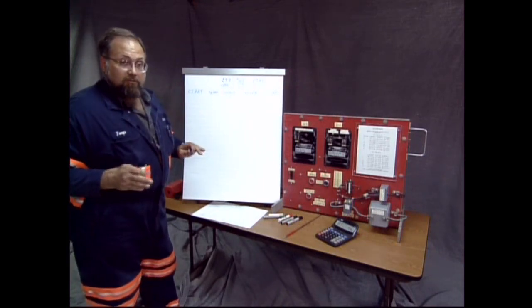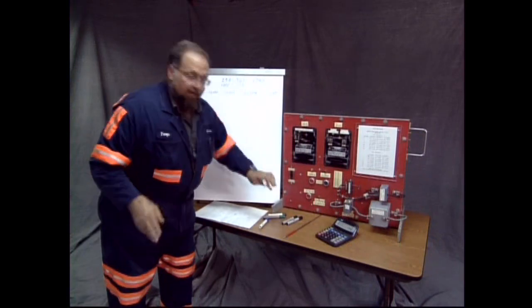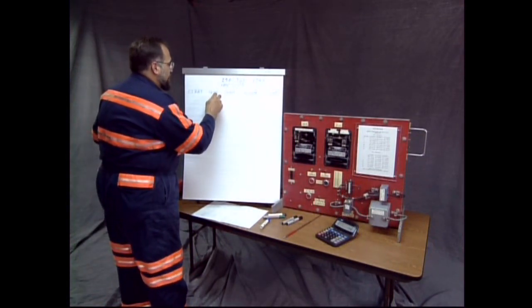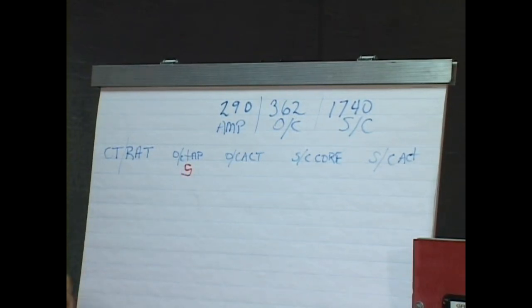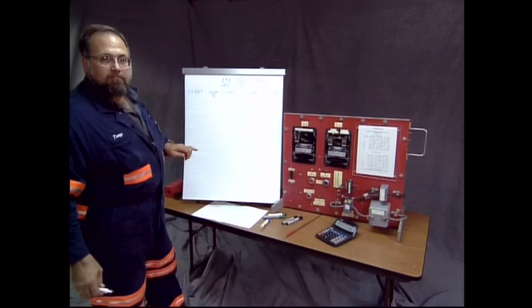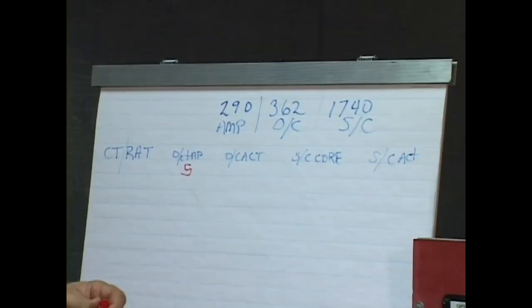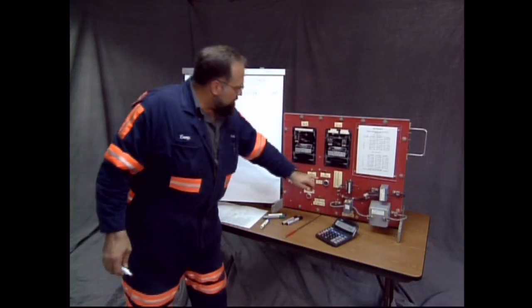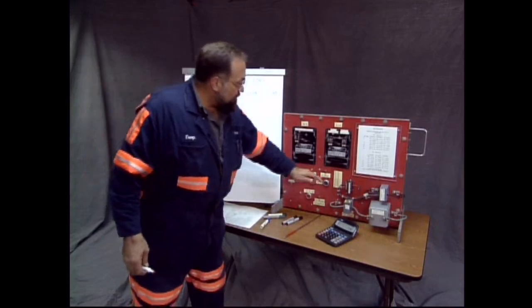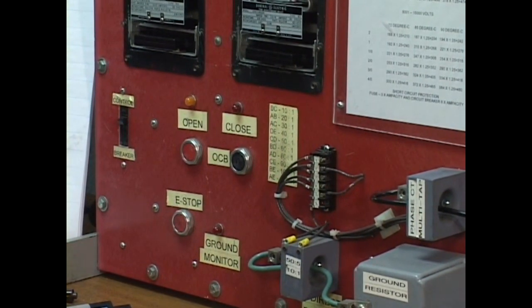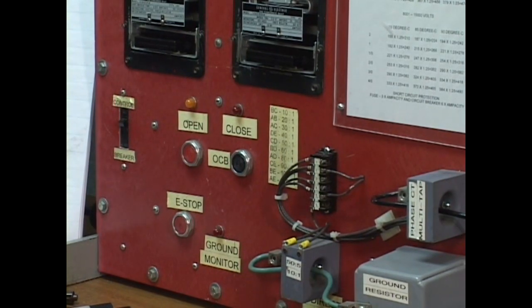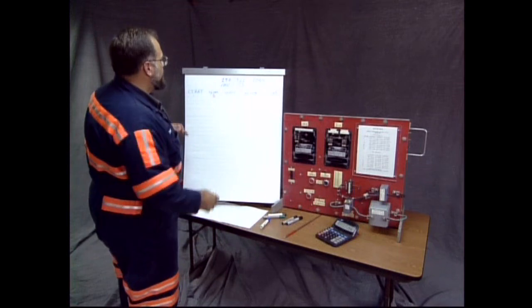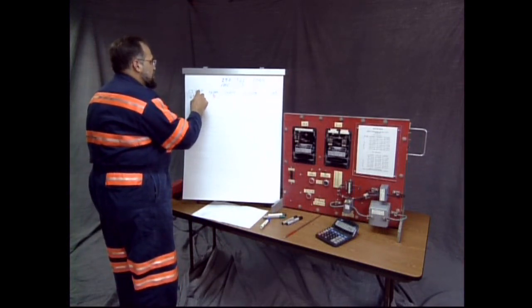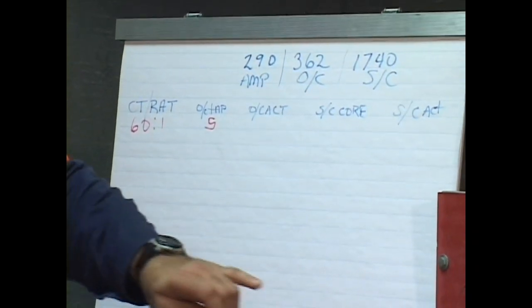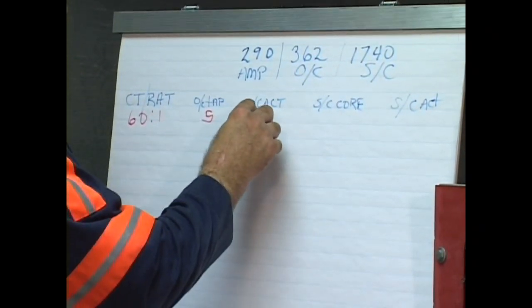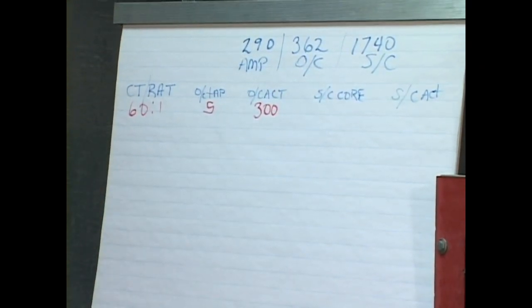The first one that you would figure, you're going to automatically choose the magic number 5. That's the ampacity of your CT secondary, magic number 5 for a tap. Now you divide your 362 by 5. What would that give you? A 70. 70 would be 350. That's as close as you can get. But we don't have a 70. All these ratios available, there are two that are missing, the 70 to 1 and the 110 to 1. They aren't available. So the next closest one I can get without going past that would be a 60. A 60 to 1 ratio. Now if I chose tap 5 and a 60 to 1 ratio, my actual setting would be 300. That's not too bad, but we may can get closer.